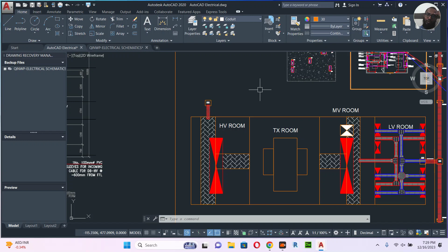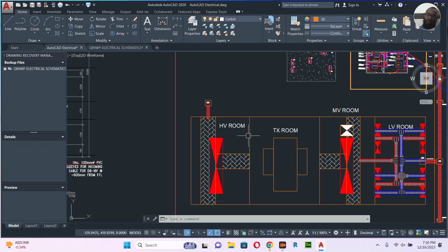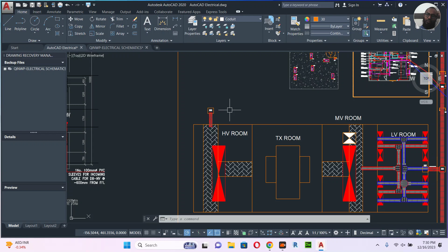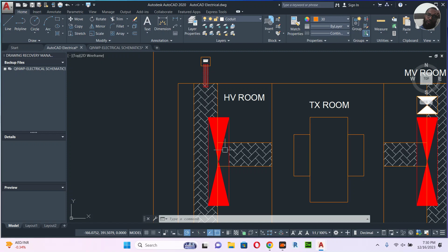So here I have 11 kV. Let's say I am using 5000 or 10,000 or 1600 kilowatts, let's say 1600 kilowatts. So I have 11 kilovolt. How many ampere will come? Very few. You have to use the formula which I told you before, but it will be a smaller ampere. So that's why the cable is smaller. The same will come to the transformer from here, and I will explain that in the single line diagram. But from here the output will be big. Normally in Qatar we sometimes use 7 cables, if it is single core, 800 cable. Why 7? 2 red, 2 yellow, 2 blue, and 1 neutral. So remember, when we are getting here, there will be no neutral.